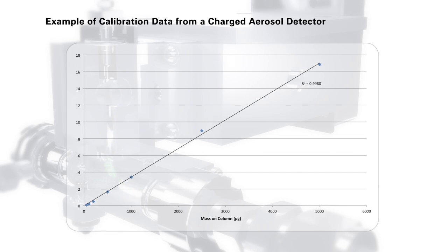Furthermore, the charged aerosol detector provides uniform relative responses. Therefore, calibration with a single standard, even if not chemically identical, can be used to estimate the amounts of all sample components.